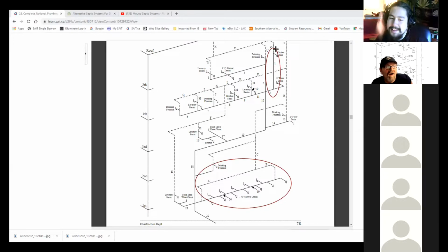Yes, this 2-inch floor drain, because it's under 3-inch, has to have a vent. So it's being wet vented through this kitchen sink. So this is a wet vented waste stack, and the 2-inch floor drain is being wet vented through it. What will be the top of the wet vented stack? Stack vent. That would be a stack vent right there, right?